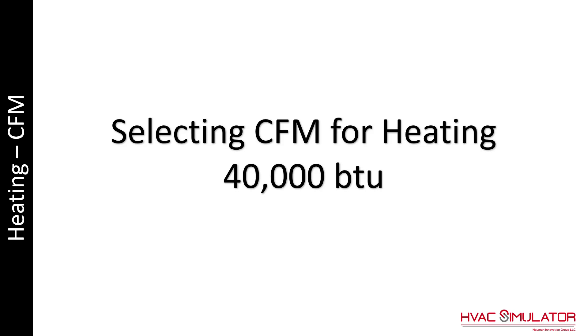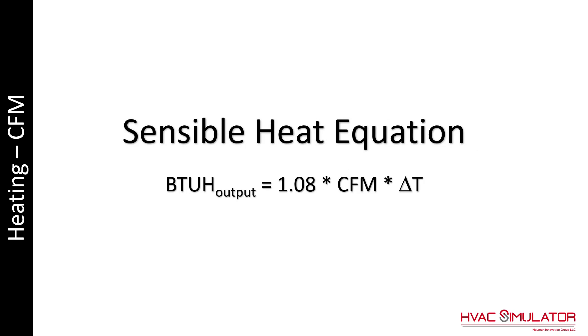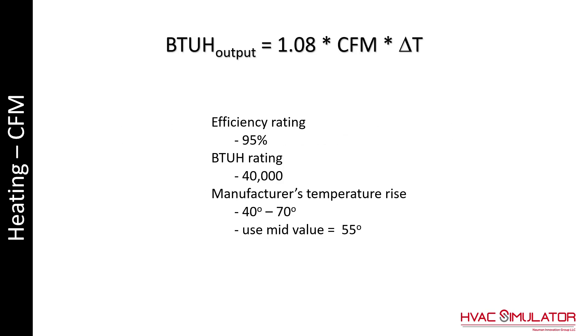Selecting CFM for heating. In this example, a 40,000 BTU furnace will be used. Begin by using the sensible heat equation. The sensible heat is much larger than the latent heat, so this formula is a good starting point. BTU output is equal to 1.08 times CFM times delta T. Items needed from the data nameplate of the furnace include the efficiency rating, the BTU rating, and the manufacturer's temperature rise. Always use the mid value — the mid value between 40 and 70 degrees is 55.